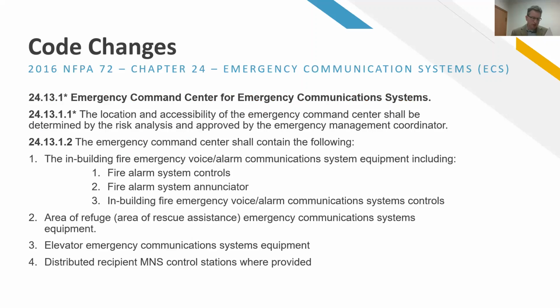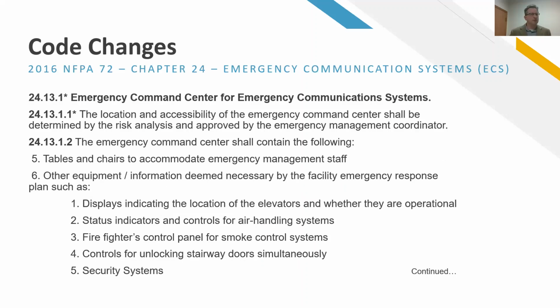And then we get into chapter 24 of NFPA 72, where there's a lot of changes, and that's for emergency communication systems. The ones that we're probably most familiar with would be like a hands-free push button two-way phone in the elevator lobby or in the stairwell or in the parking ramp. And those are emergency communication systems, and they come in different shapes and forms. But there are some requirements that address that, when previously there wasn't much in the code that really said much about emergency communication systems. Now we do have some requirements that we have to adhere to, so we've got to be careful that we're being code compliant in that respect.